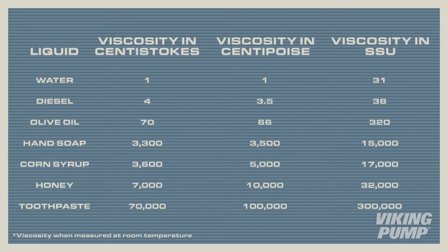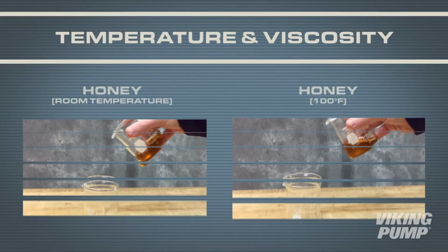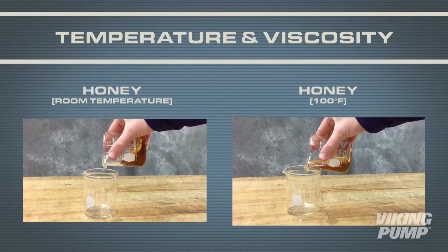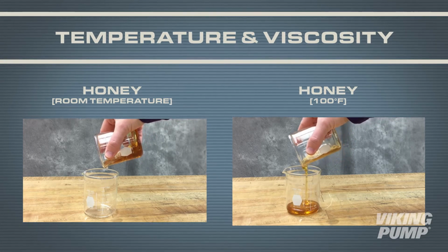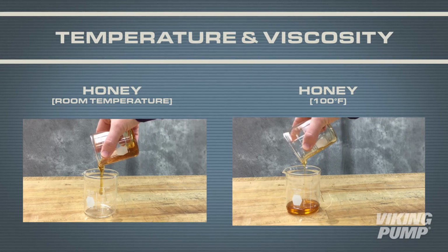Here are some common liquids and their viscosities at room temperature. Remember though, temperature has a big impact on viscosity. With very rare exception, the colder the temperature, the higher the viscosity. It's important that the viscosity measurements you take are done at the pumping temperature.